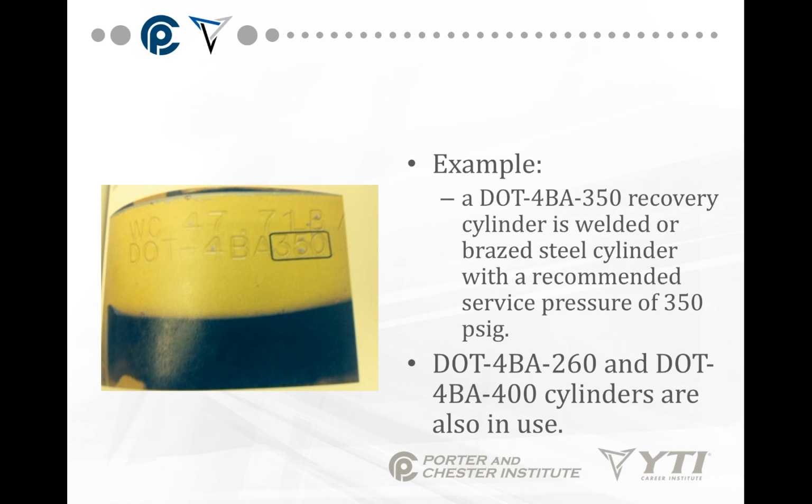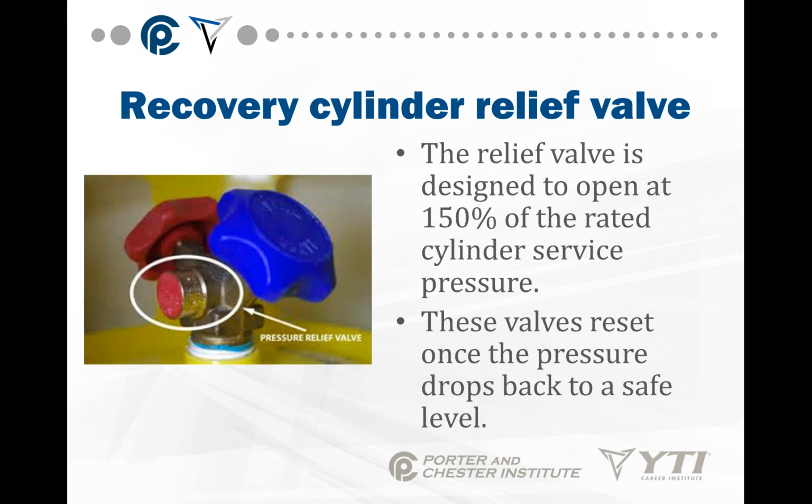Okay, so again, DOT controls the recovery cylinders. The relief valve is designed to open at 150% of the rated pressure, and these valves reset once the pressure drops back to a low level. So again, be careful with refrigerants, know the safety requirements, review the MSDS, and whatever you do, do not inhale or get liquid refrigerants on your skin.